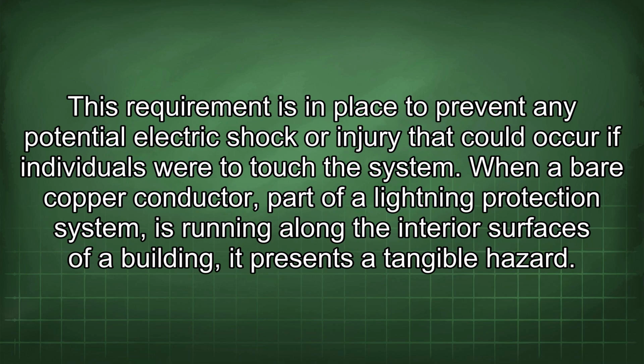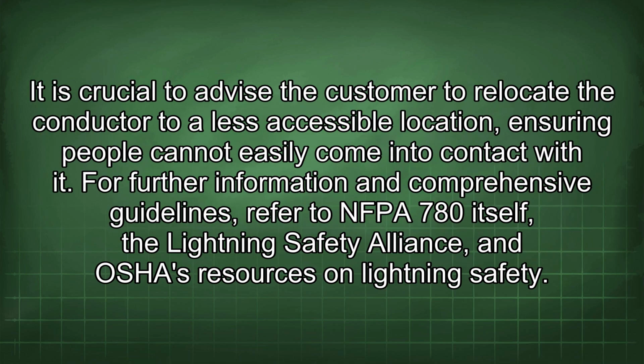This requirement is in place to prevent any potential electric shock or injury that could occur if individuals were to touch the system. When a bare copper conductor, part of a lightning protection system, is running along the interior surfaces of a building, it presents a tangible hazard. It is crucial to advise the customer to relocate the conductor to a less accessible location, ensuring people cannot easily come into contact with it.